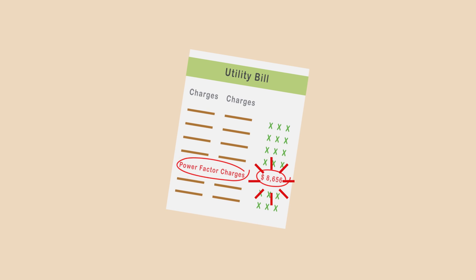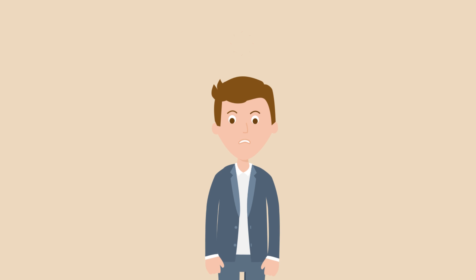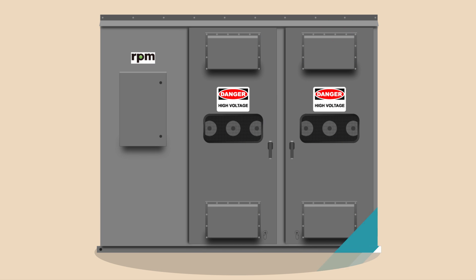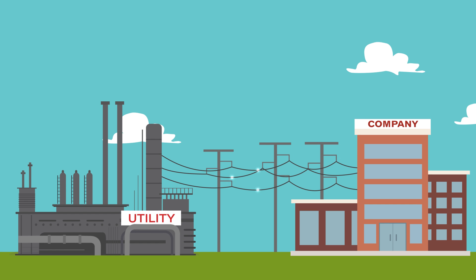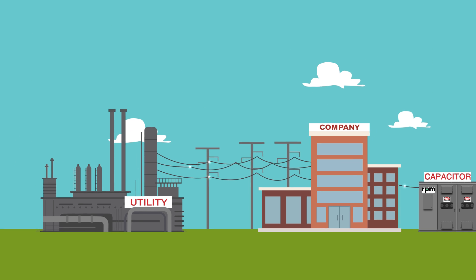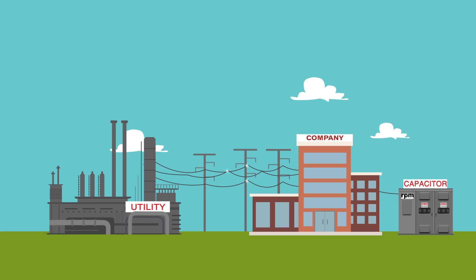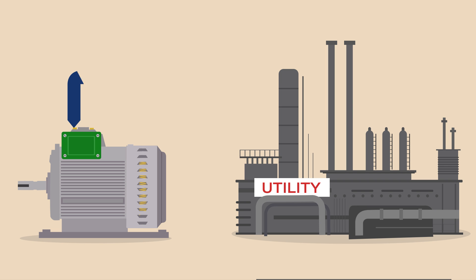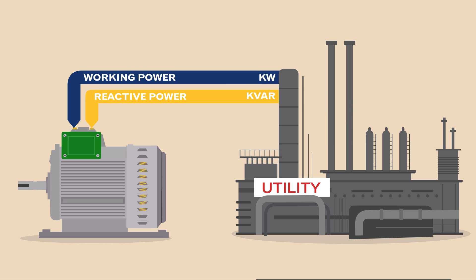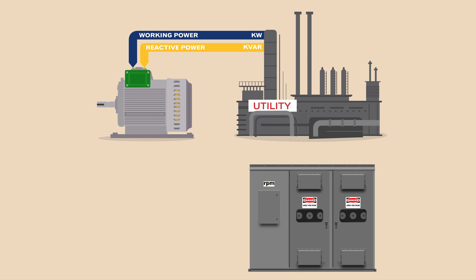How do you get rid of the charge? By installing power factor correction capacitors. These temporary storage units provide reactive power to your motor instead of receiving it from the utility. Both kW and kVAR come from the utility, but when a capacitor is installed in your facility, it replaces the reactive power supplied by the utility.